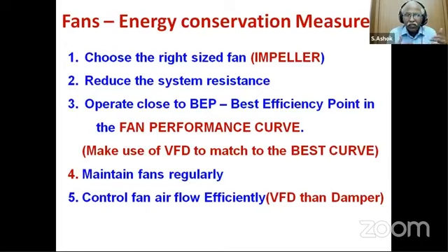And next, is the fan going to operate at the best efficiency point, whether the system curve and the static pressure curve are matching, at which point, that is going to be the best efficiency point for the given fan AHU, and are we close to the best efficiency point. If it is not there, this can be improved by retrofitting a VFD, and it is best to select or facilitate the best possible curve. Maintain the fans regularly and control the airflow efficiently, going for a VFD instead of a damper.